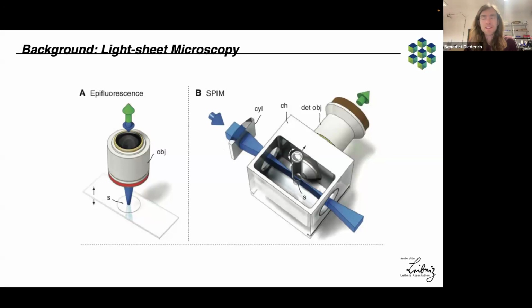In microscopy, there's a solution to that. Also in the real world, 3D scanners work very similarly. You create a two-dimensional sheet, which illuminates your sample from the side, and then you detect only the part that is being illuminated with an objective lens oriented perpendicular to the light sheet. Then you scan the sample through this light sheet, and similar to an MRI, you have several slices, and then you can reconstruct the three-dimensional shape as a volumetric image.